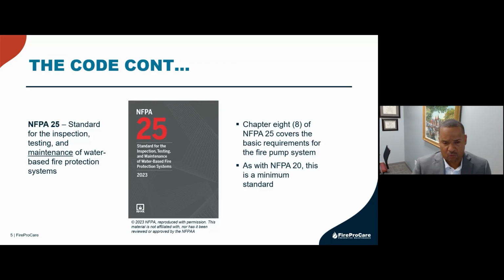NFPA 25 was, again, one of those standards on that first page I showed you. It talks about the standard for the inspection, testing, and maintenance of the fire protection system. And to be more specific, what we do when it comes to the fire pump equipment is covered in Chapter 8 of NFPA 25. We're going to dive a little deeper into that, but I want you to remember NFPA 25 is also the minimum standard. So if you have something local, or you have something that's been approved by your authority having jurisdiction that meets or exceeds NFPA 25, you're certainly welcome to use that, but you need to get that approved by the AHJ.